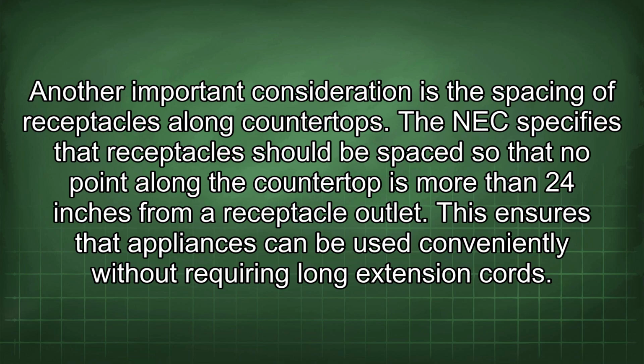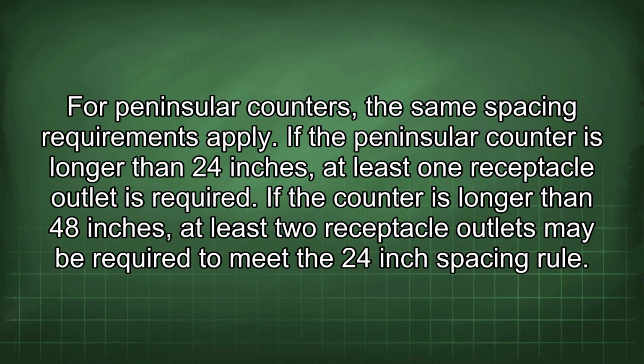Another important consideration is the spacing of receptacles along countertops. The NEC specifies that receptacles should be spaced so that no point along the countertop is more than 24 inches from a receptacle outlet. This ensures that appliances can be used conveniently without requiring long extension cords. For peninsular counters, the same spacing requirements apply. If the peninsular counter is longer than 24 inches, at least one receptacle outlet is required. If the counter is longer than 48 inches, at least two receptacle outlets may be required to meet the 24-inch spacing rule.